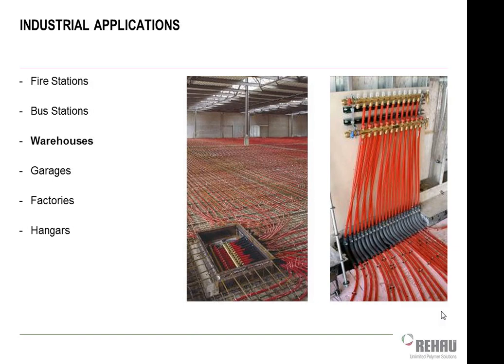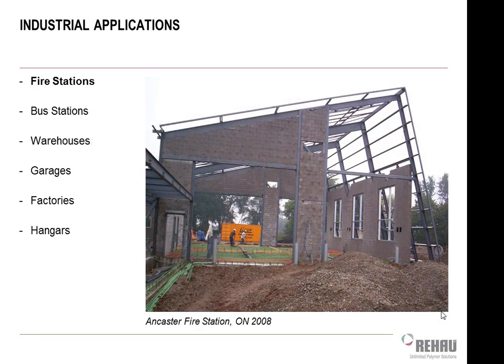There's just photos here we're showing you of laying some of these tubing systems out. Fire stations very often do radiant flooring. Even if they don't do it on the whole building, they very frequently will do it nowadays in the dock area. Once again, when those fire trucks lift up the dock doors, they fly out of there, they tend to leave those doors up for the next hour while they're on a call or whatever they're doing. And if you heated the air in that space, all the energy would get sucked out of there very quickly. If you do radiant heating, you're not heating air, you're heating objects, and it tends to save energy even when the doors are open. So fire stations, bus stations, warehouses all do it for that type of reason.